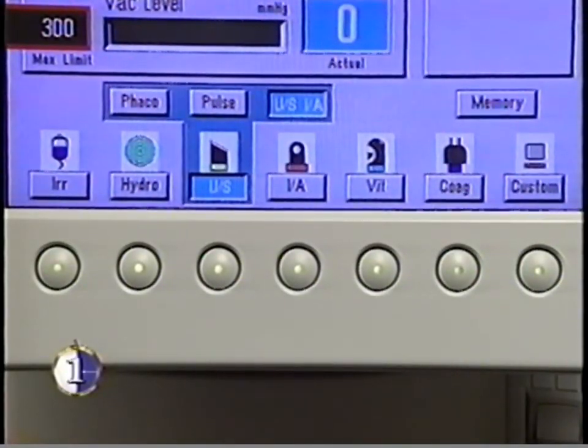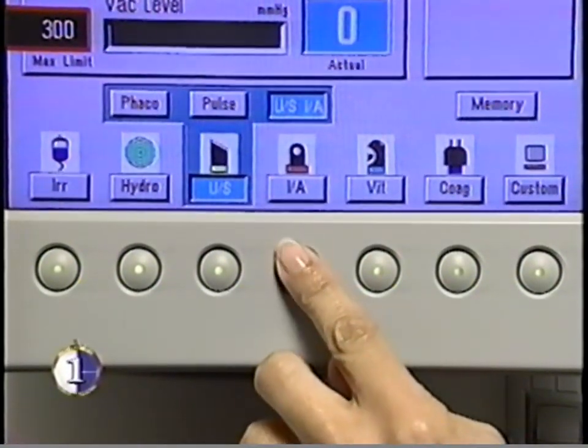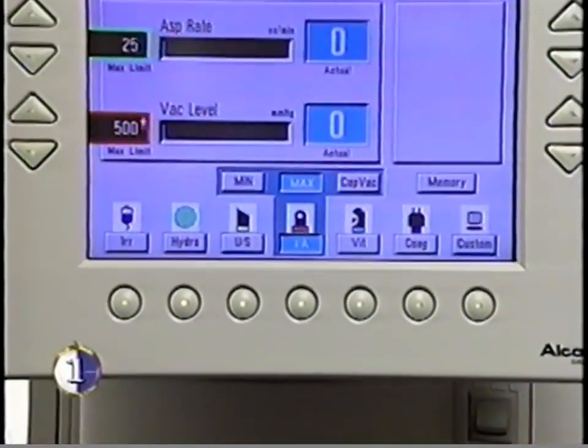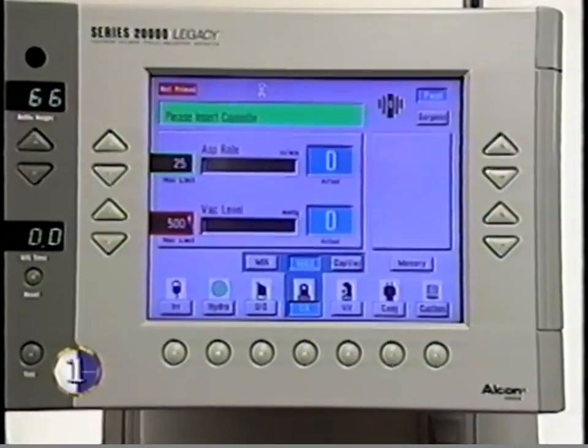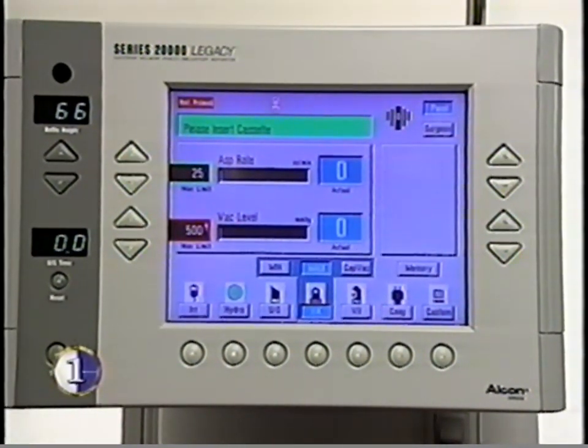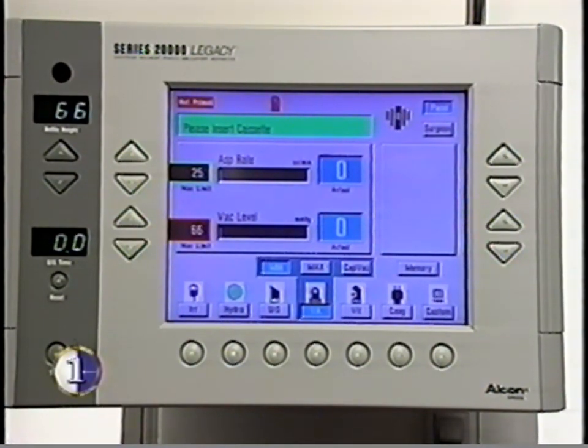The irrigation aspiration mode is used for cortical cleanup after the cataract has been removed. Primary parameters are aspiration rate and vacuum level. IA submodes are IA max and IA min, in which the operator can adjust the preset aspiration and vacuum limits from the control panel. Both panel and surgeon control are available in these submodes to provide irrigation or simultaneous irrigation and aspiration via the foot switch.